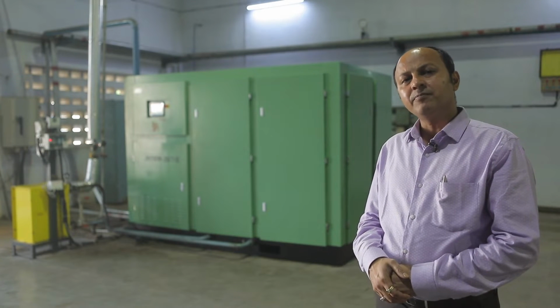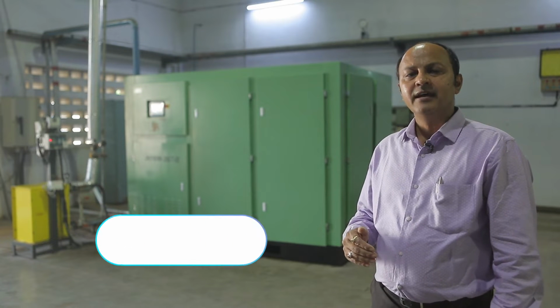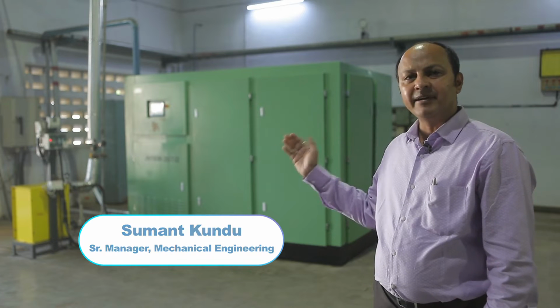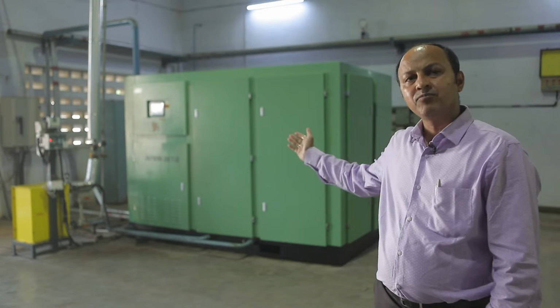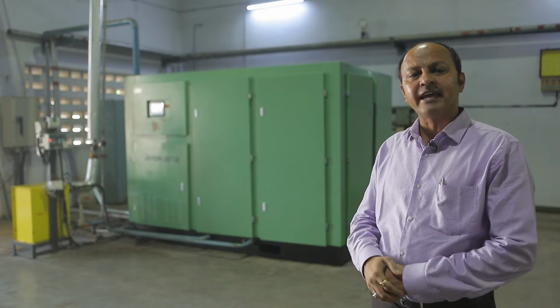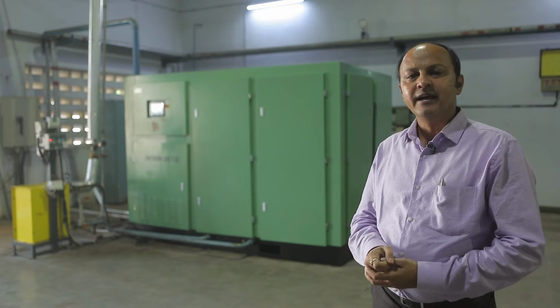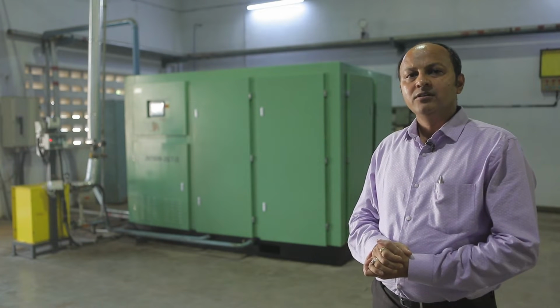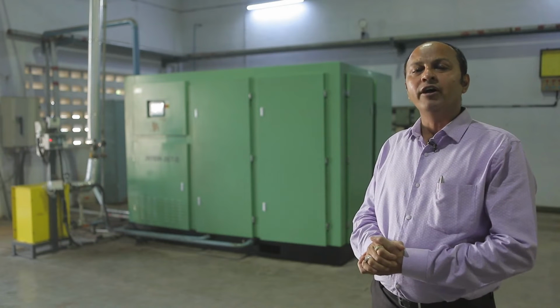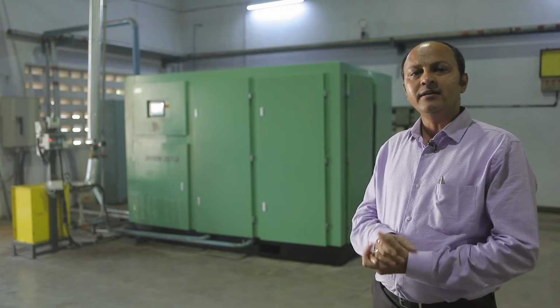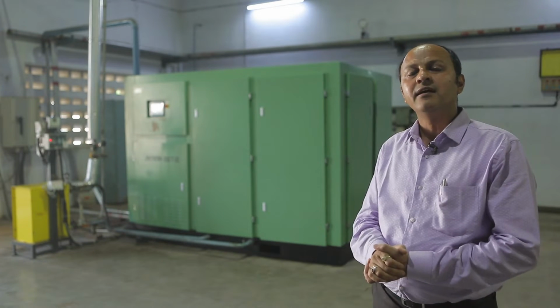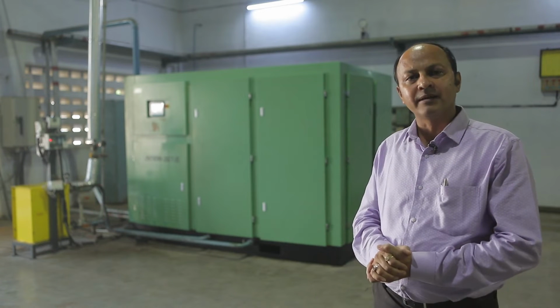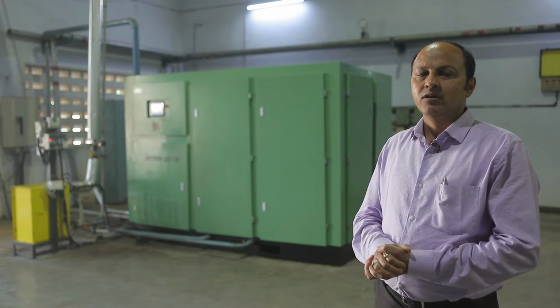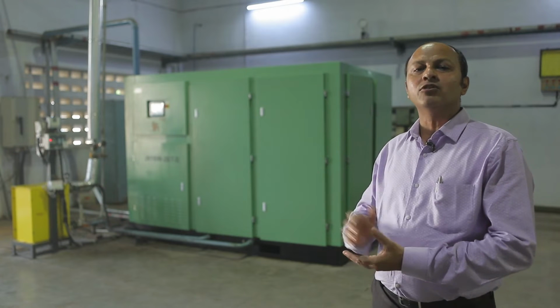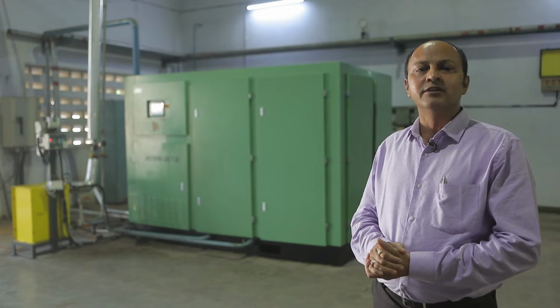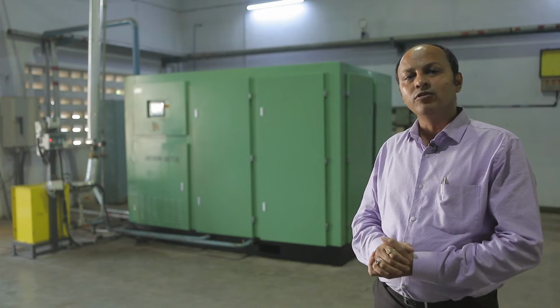In any compressed air system, air compressors consume almost 90% of its energy and it is as a waste coming out. Here we have implemented a waste heat recovery system on our compressor. This is the compressor. So we have installed a waste heat recovery system by which we are capturing out of that 90% of waste heat and we are converting it as a hot water generator. This compressor is using the oil and oil is getting heated by capturing the heat. That oil is transferring the heat into this waste heat recovery heat exchanger and by that we are getting almost 60 kilowatt per hour capacity waste heat recovery. For the monitoring purpose, it is beneficial not only for the carbon footprint but also it is reducing the water footprints also. It is also reducing the load into the cooling tower.